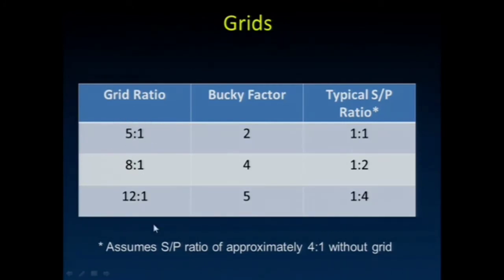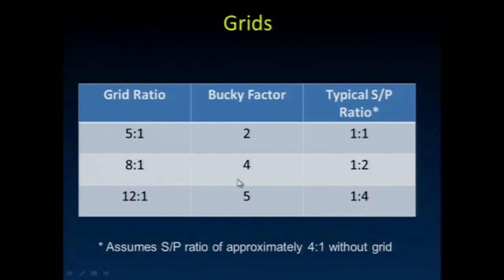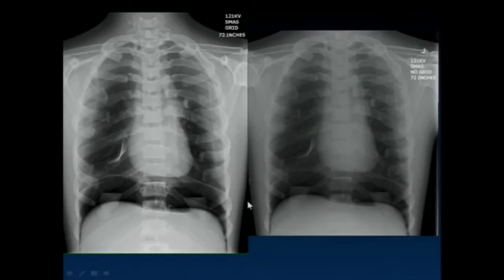For grid ratios of 5, 8, and 12, notice that the grids convert a four-to-one scatter-to-primary ratio to a one-to-four scatter-to-primary ratio. But the price paid is a need for a five-times increase in dose to the patient.